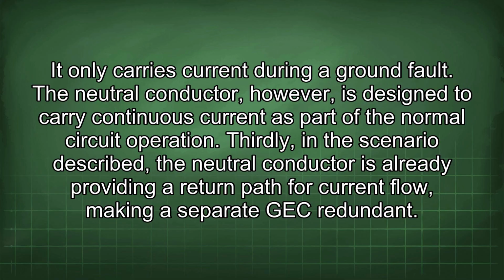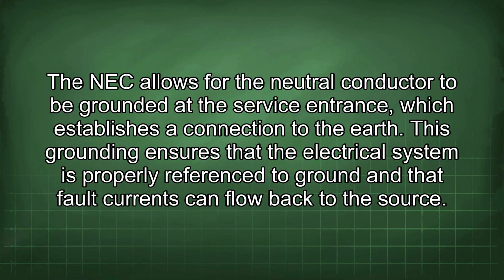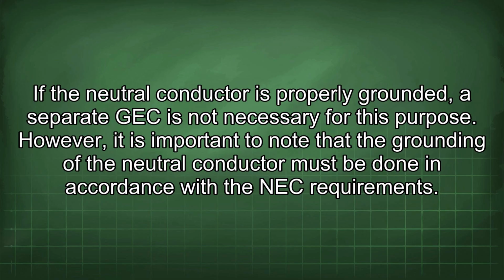Thirdly, in the scenario described, the neutral conductor is already providing a return path for current flow, making a separate GEC redundant. The NEC allows for the neutral conductor to be grounded at the service entrance, which establishes a connection to the earth. This grounding ensures that the electrical system is properly referenced to ground and that fault currents can flow back to the source. If the neutral conductor is properly grounded, a separate GEC is not necessary for this purpose.